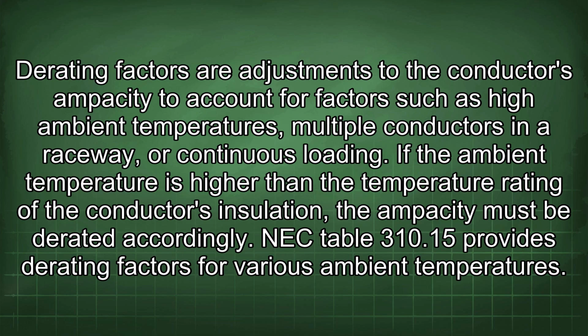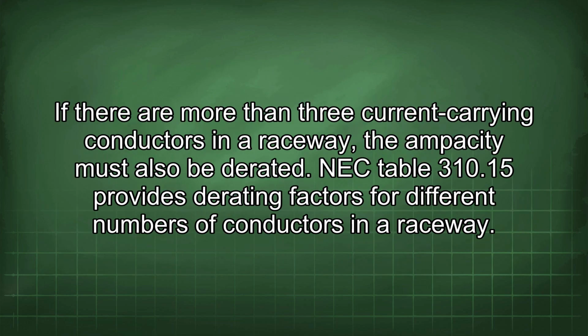If the ambient temperature is higher than the temperature rating of the conductor's insulation, the ampacity must be derated accordingly. NEC Table 310.15 provides derating factors for various ambient temperatures. If there are more than 3 current-carrying conductors in a raceway, the ampacity must also be derated. NEC Table 310.15 provides derating factors for different numbers of conductors in a raceway.